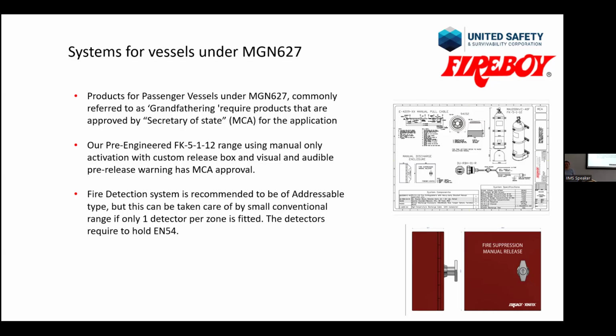So the requirement there is for a pre-engineered fire suppression system, but it has to be manual operation only. It has to give you audible and visual warning. To be able to provide all of that, we use our standard pre-engineered range with manual only activation, where the red handle of the pull cable is fitted in the red box, which has got a micro switch inside. So when you open the box to go and activate the extinguisher, it will set off a sounder fitted inside of the protected space with the warning notice, giving everyone warning that the discharge is imminent.